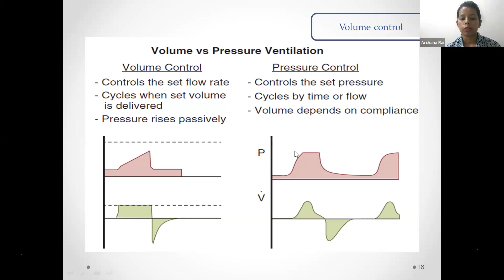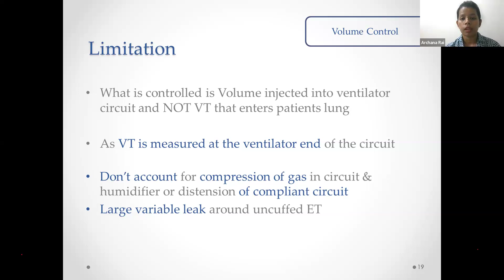But there were some disadvantages with the volume control mode, because the volume which is measured is usually what is being injected into the ventilator, that is at the ventilator end of the circuit, and not what is entering the baby during inspiration or expiration. Secondly, it doesn't account for the compression of gases that occurs in the circuit and the humidifier, and also the circuit's compliance may change. Thirdly, it also doesn't account for the variable leak, which can be very large because of the uncuffed ET tube used in neonates. So volume control mode usually doesn't work if the leak is more than 50%.